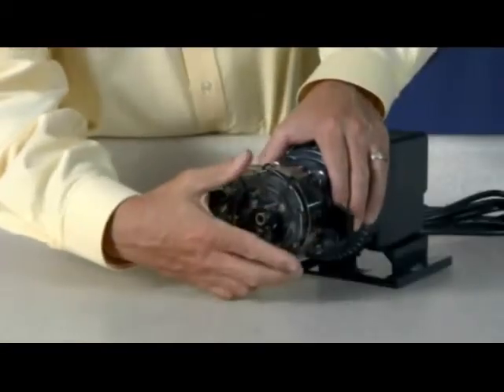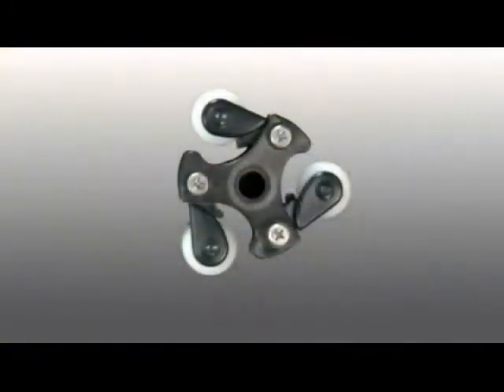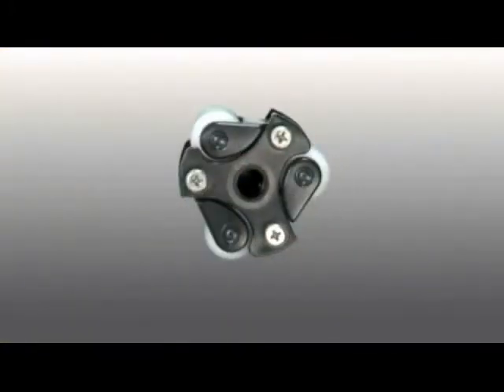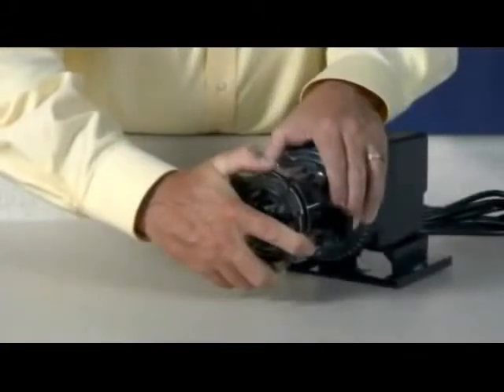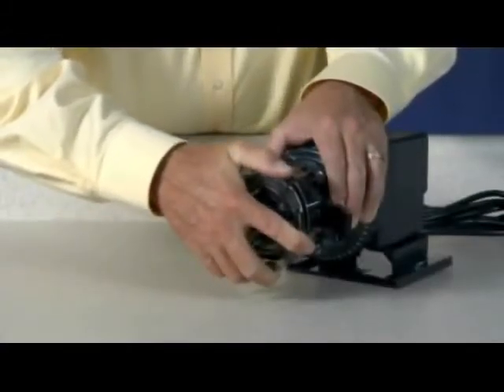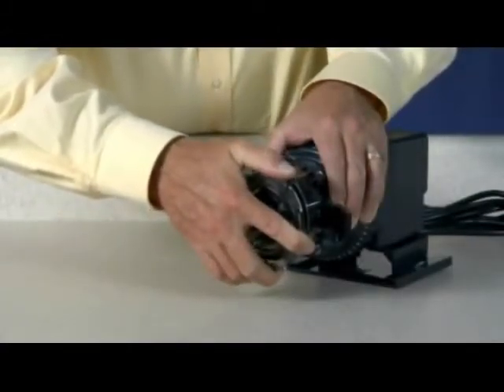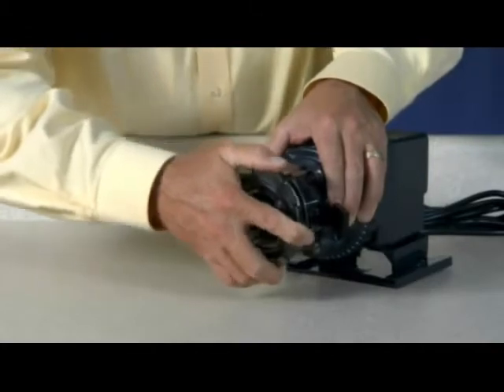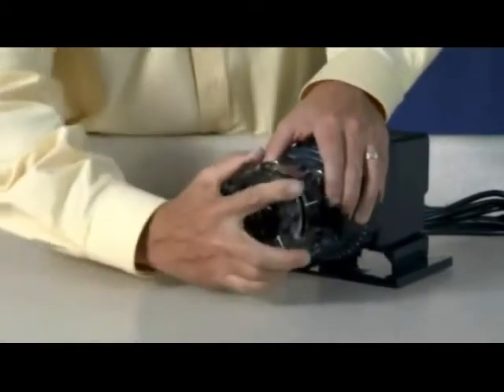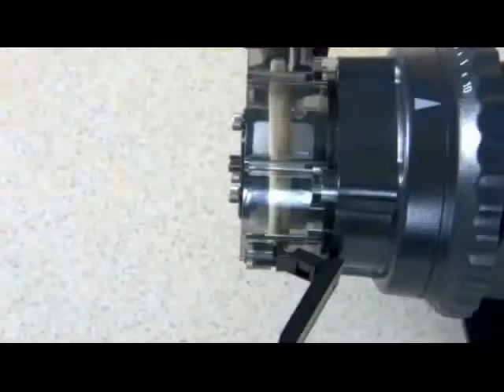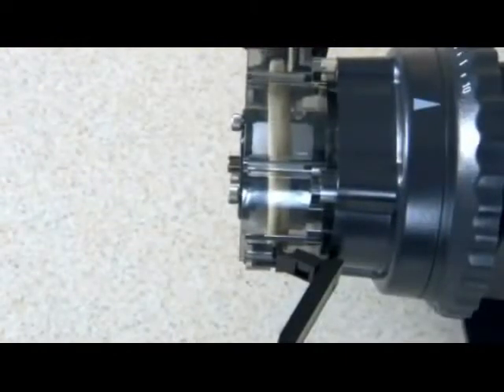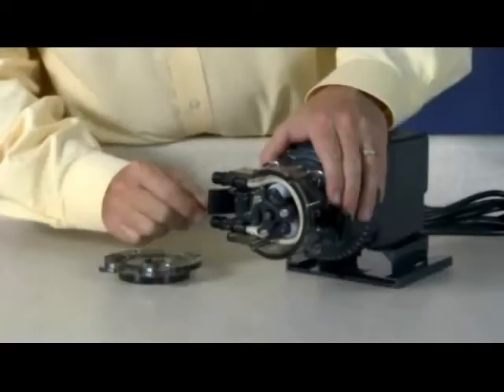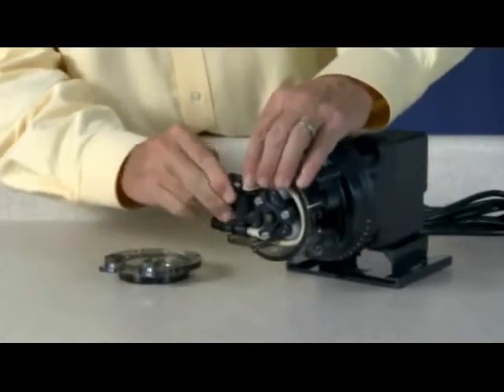Position the cover feet near the tube fittings. The roller assembly needs to be collapsed to remove the tube. Hold the feed rate control securely. Use the tube housing cover as a wrench and quickly snap. Rotate the cover counterclockwise to collapse the roller assembly. The tube will no longer be pressed against the tube housing wall. Remove and discard the pump tube.